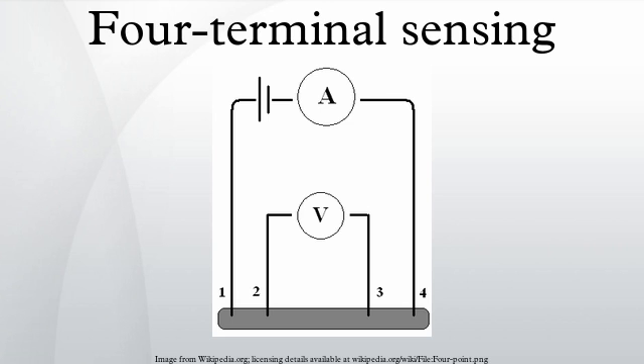It is usual to arrange the sense wires as the inside pair, while the force wires are the outside pair. If the force and sense connections are exchanged, accuracy can be affected, because more of the lead resistance is included in the measurement.